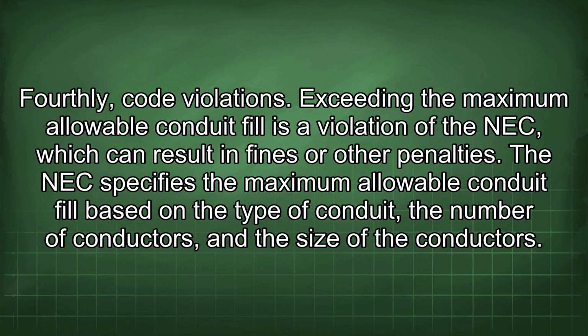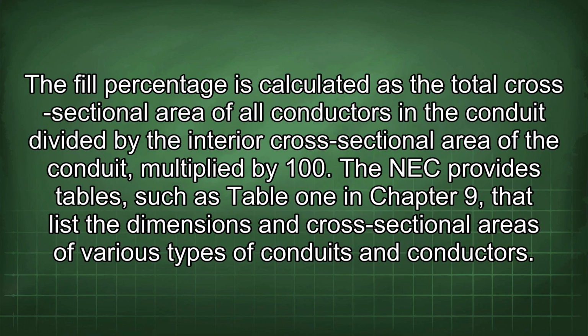The NEC specifies the maximum allowable conduit fill based on the type of conduit, the number of conductors, and the size of the conductors. The fill percentage is calculated as the total cross-sectional area of all conductors in a conduit divided by the interior cross-sectional area of the conduit, multiplied by 100. The NEC provides tables, such as Table 1 in Chapter 9, that list the dimensions and cross-sectional areas of various types of conduits and conductors.